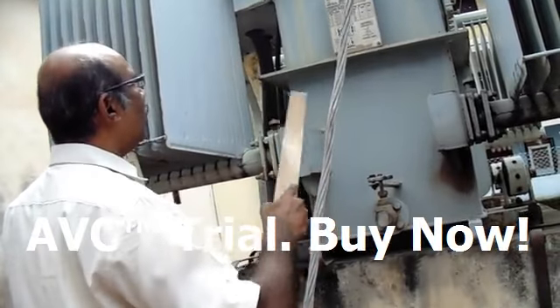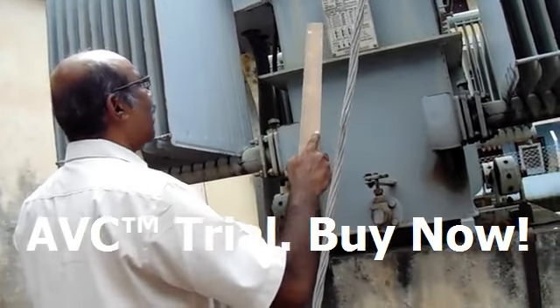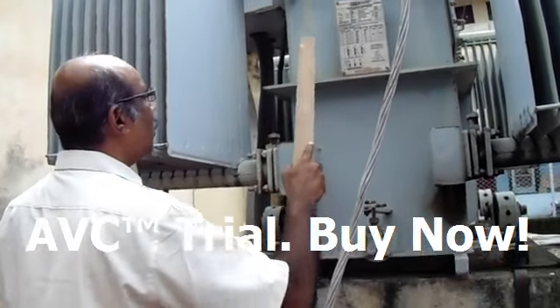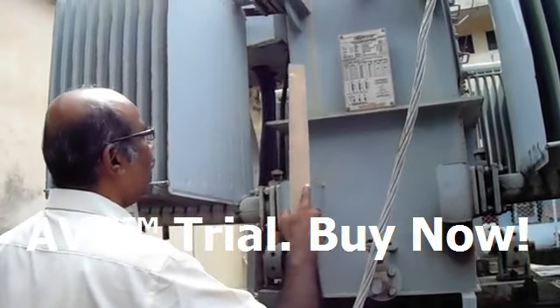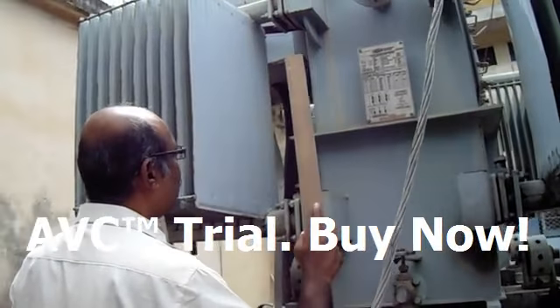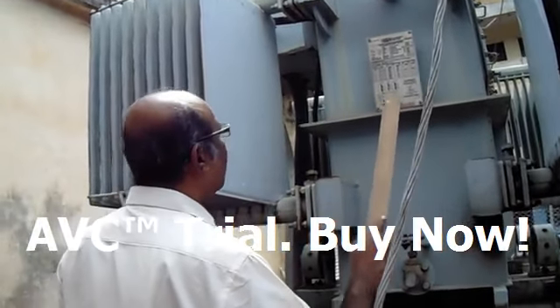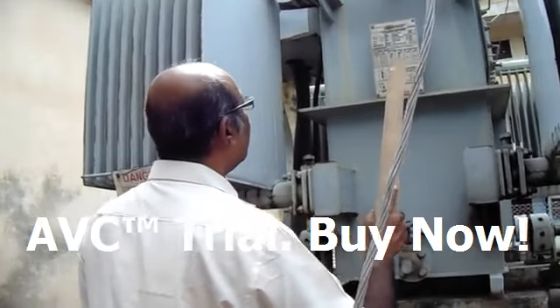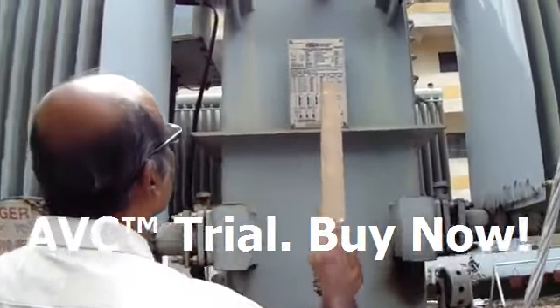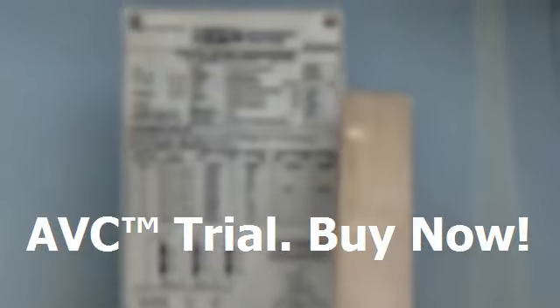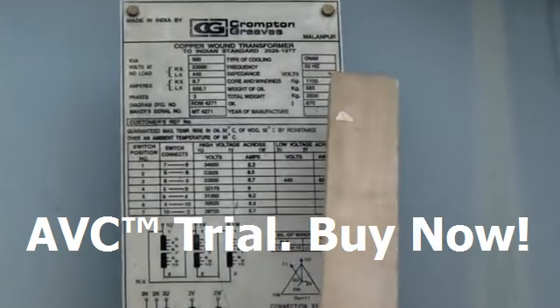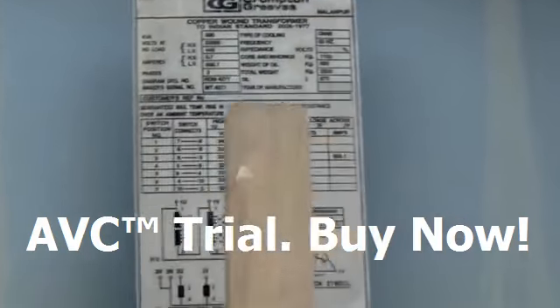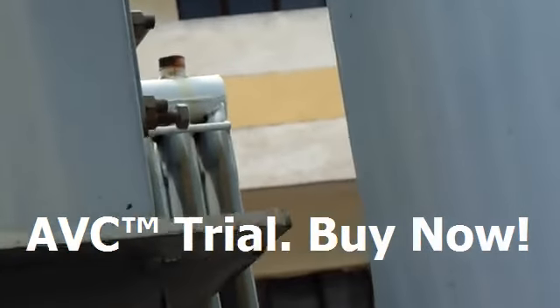So this is a natural convection which is taking place in the transformer, and the cooling takes place with that. There is a transformer oil which we use in the transformer tank, and you can see that the weight of that is given somewhere here. The weight of the transformer, the weight of oil is 585 kg, and the total weight of the transformer including this oil is 2.5 tons. You can see over.